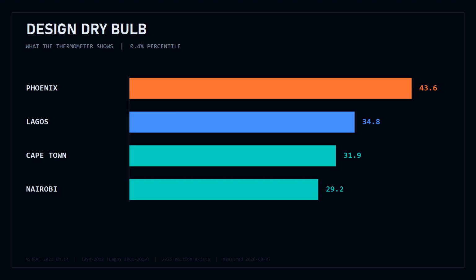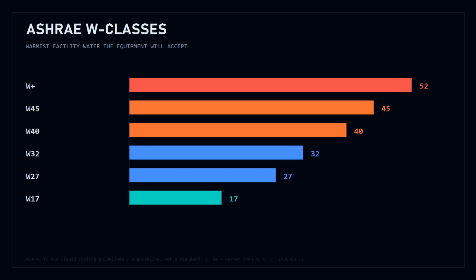ASHRAE's thermal guidelines class liquid-cooled equipment by the warmest water it will accept. W27 wants water no warmer than 27 degrees. W45 will take 45. So the question stops being how cold can I get the water and becomes which class will this city support with this machine without a chiller?